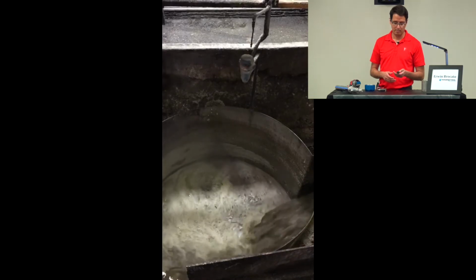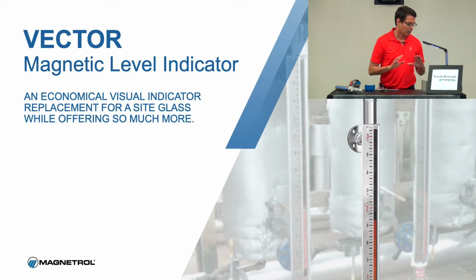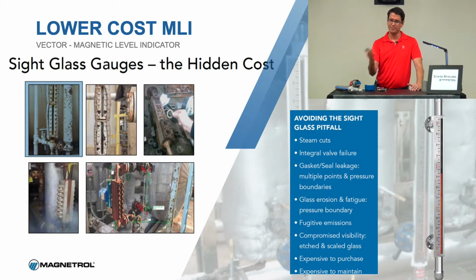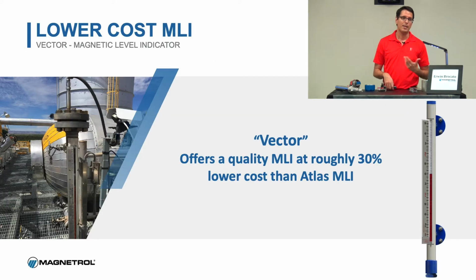All right, so moving on to magnetic level indicators. Low-cost magnetic level indicators. Basically, magnetic level indicators are going to try to replace your common sight glass. I think I was talking about this before. It may fall under the mechanical component in a facility, but any kind of tubular or reinforced sight glass could be a safety hazard. It may be compromised by somebody hitting it, or over time the glass deteriorates, or something happens and you have a steam leak or some kind of leak of a product, and you do not want a leak of something toxic or lethal, or high pressure steam, obviously. So magnetic level indicators replace these sight glasses, and we offer a higher safety product that also requires less maintenance, because you don't have to replace the glass over time. So there's an advantage to these MLIs, the magnetic level indicators.